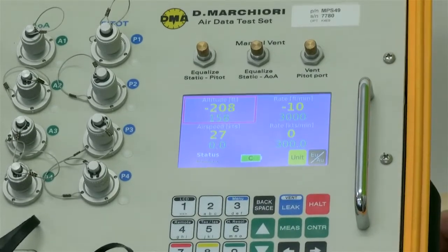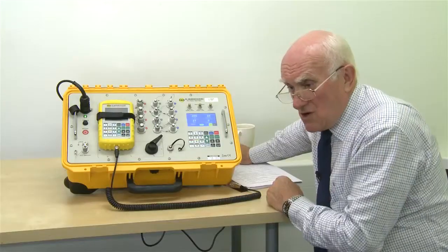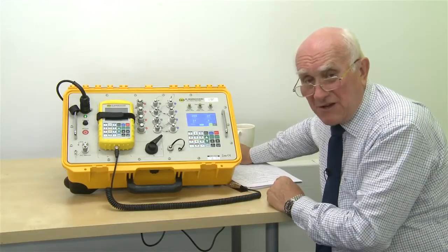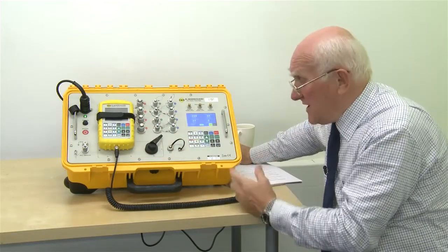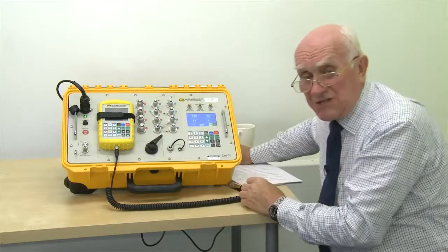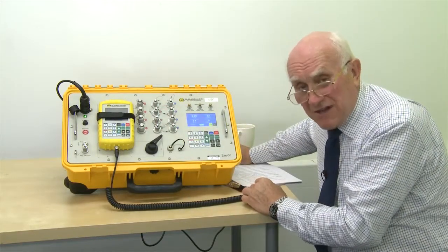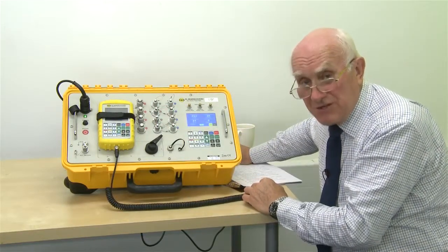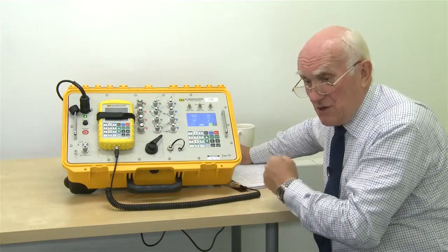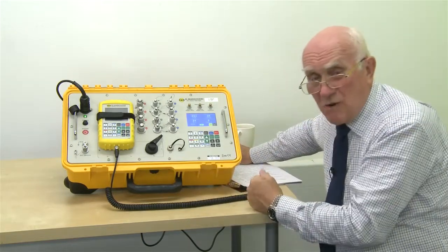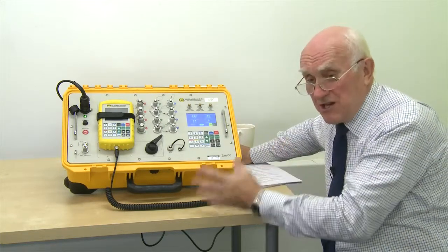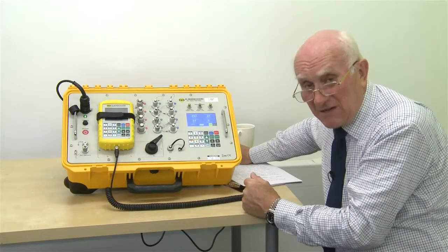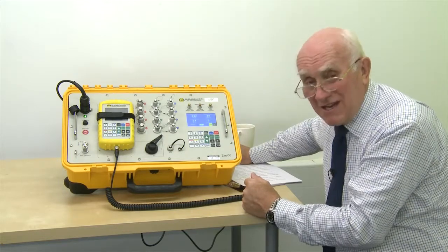We move on then to the top. They're the manual letdown valves. Generally speaking, they're probably never going to be used because the instrument comes with the capability to run on internal batteries, and the batteries will give you 2 hours of operation. This means that you can use the instrument if you wish away from AC supplies, and in addition, should you actually lose the power in the middle of a test, you won't see any difference.